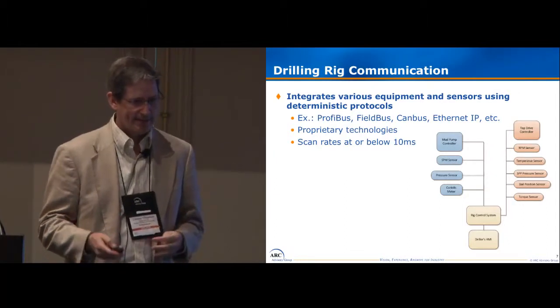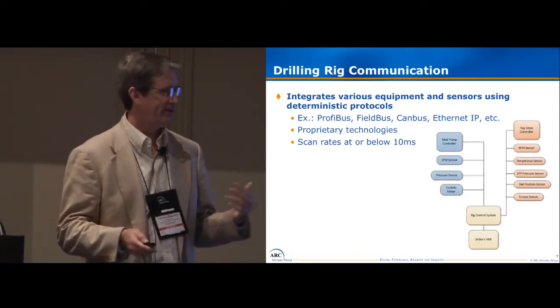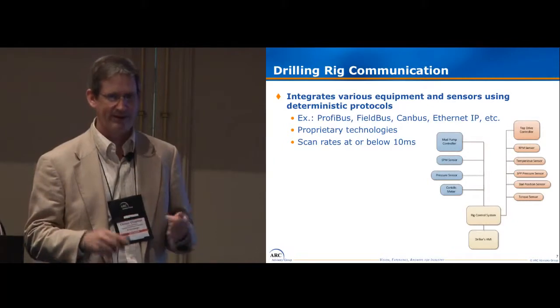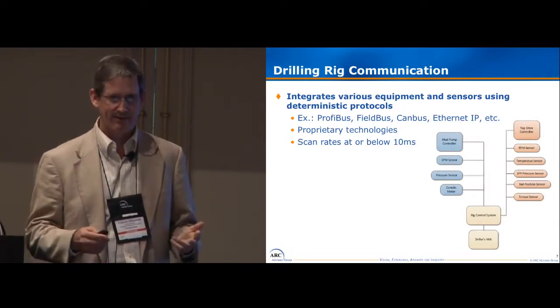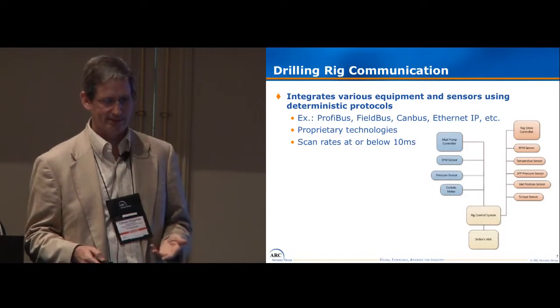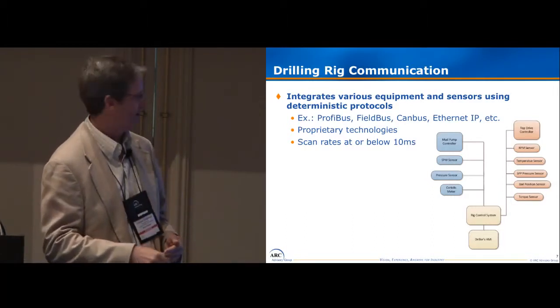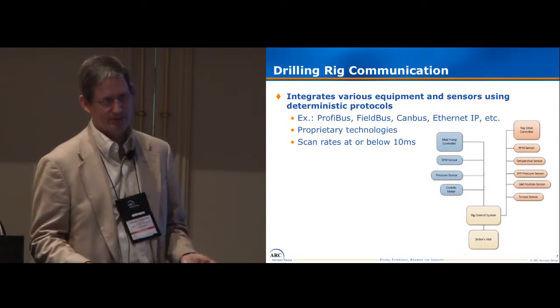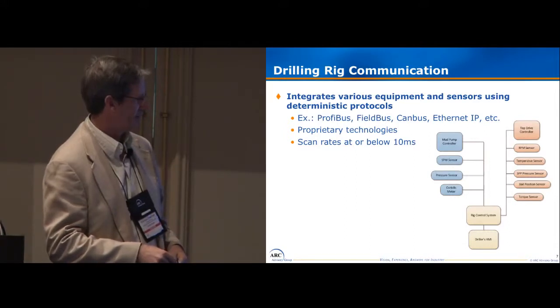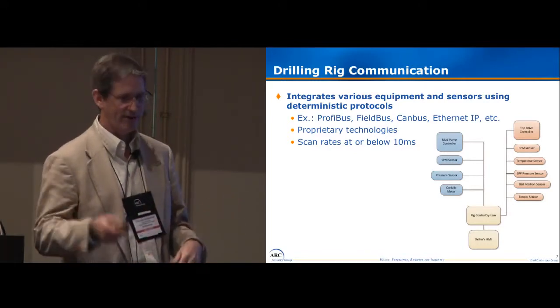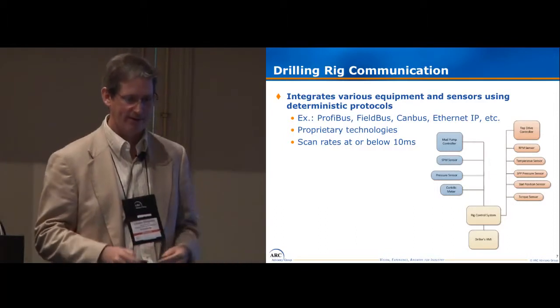Drilling rig communication is complex — every rig seems to be different, varying by manufacturer. You have all the field bus technologies: Profibus, FieldBus, CAN bus, Ethernet IP, a whole host of homegrown systems and standards. Proprietary technologies and scan rates are generally around 10 milliseconds. You have a mud pump controller connected to strokes-per-minute counters and pressure sensors, and a top drive controller with RPM sensors and temperature sensors — all fed back to a rig control system, usually integrated into one. But there are cases where the pump control has nothing to do with the top drive control — it's completely unintegrated.